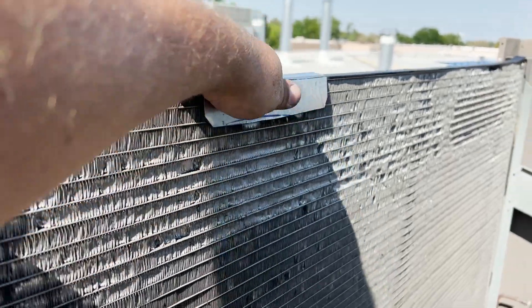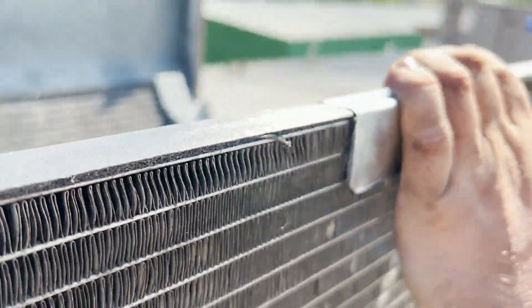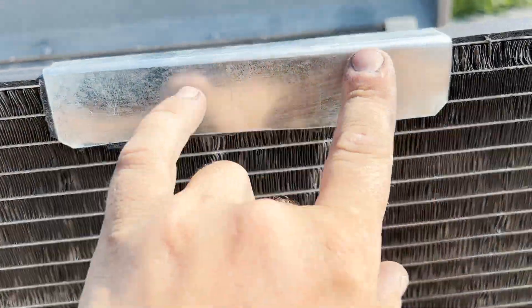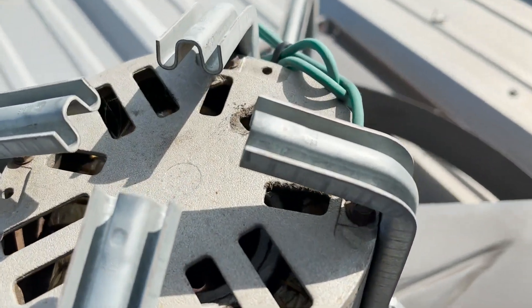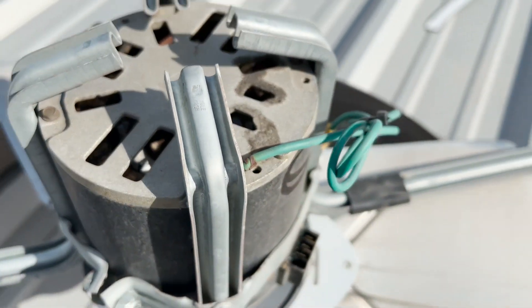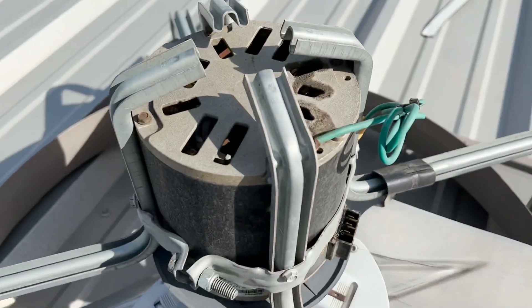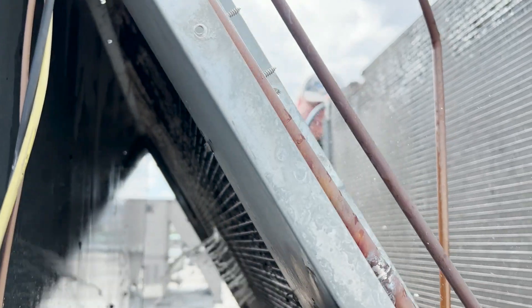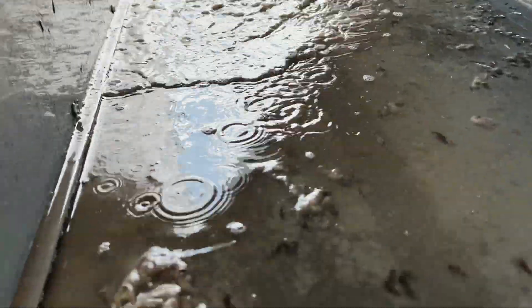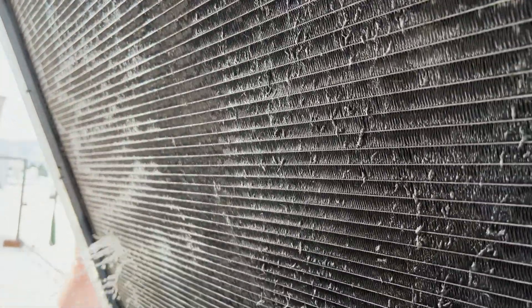That should cover our patch nicely. We don't actually have the two metals touching — we've got foam on foam, and no air is going to get through that hole we made. Something worth noting: these don't last forever. This issue we had here is kind of caused by vibration, so lack of oil in the bearings could be a contributing cause for sure.